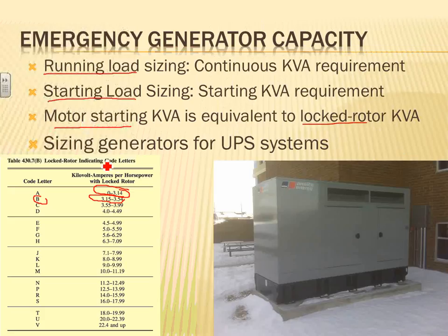Okay, so that's the UPS sizing. I don't know, Tom, you remember the size used to be, if you have a UPS, you have to double the size of the generator, right? Double the size of generators. The last time I heard it is 1.5. So if you want to pick up a UPS, you have to make the generator 50% bigger than the size of the UPS. That's sort of your rule of thumb. Some of the bigger UPSs can become closer to one-to-one. It all depends on the UPS and how much feedback it's getting. So between 150 to 200 basically of the size.